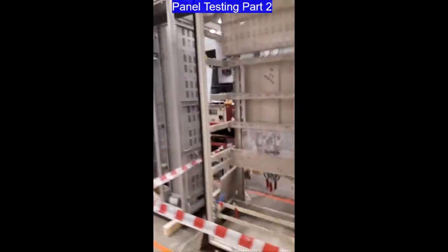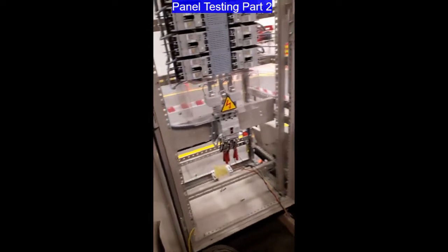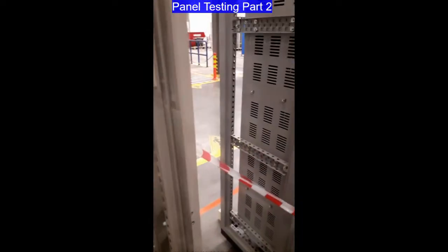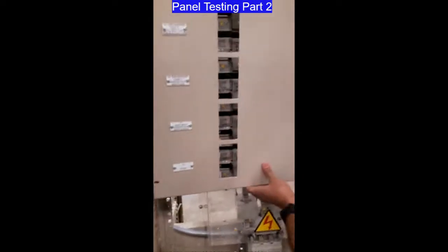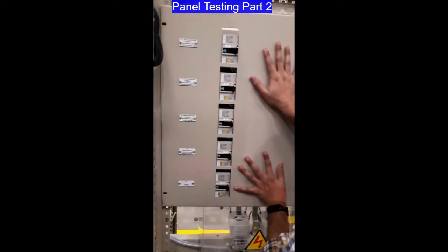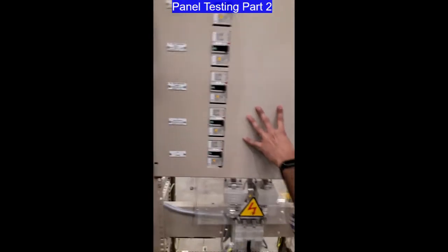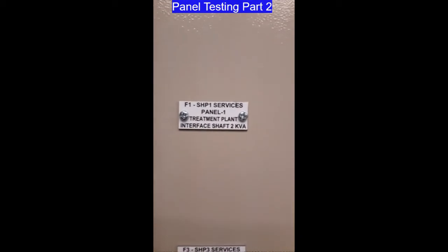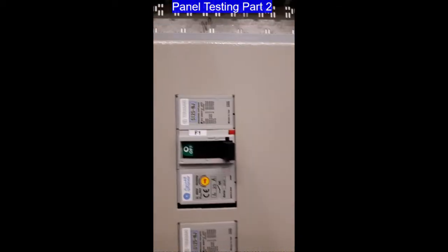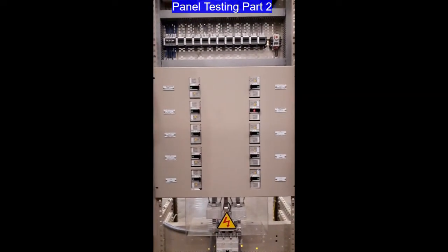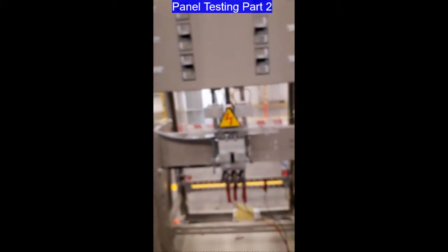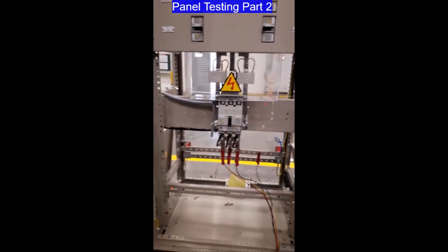Okay, now we are going to check the load details of each branch breaker. For example, this is our DFC, what we call the dead front cover. The load details for F1 are available here in our approved drawing, which is what we follow. That is for F1 and so on. Those all have load details also. And on our main breaker, we will provide it later on the cover.